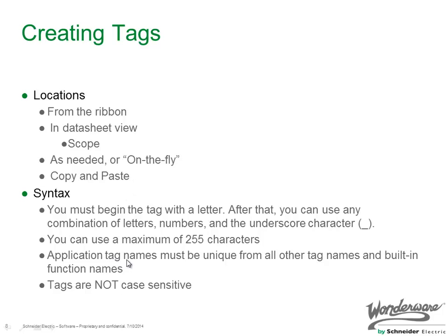Application tags, project tags, must be unique from all other tag names and built-in function names, so you can't have tags that match some of the system tags or some of the built-in scripting functions. And an important thing to note is tags are not case sensitive.